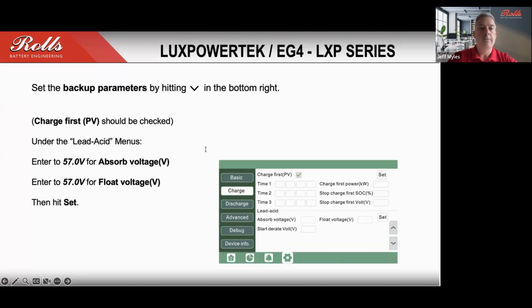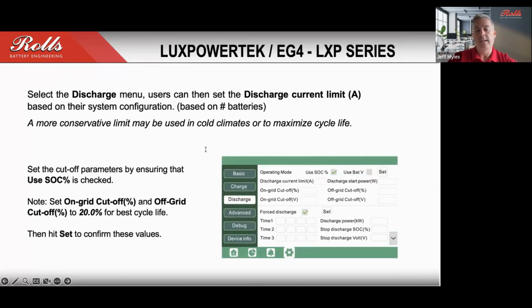And so the voltage for absorption, you're going to set that at 57. In the case of float voltage, for those of you who've worked with lead acid in the past, generally you'd have a float that would be slightly lower than your charge voltage. In this case, you're just going to set it at 57 as well. So you're walking through those voltage settings, and then once you complete that, you're going to see on the screen that closed loop communication has been established. And so you're going to see right away that that communication has been set up correctly.